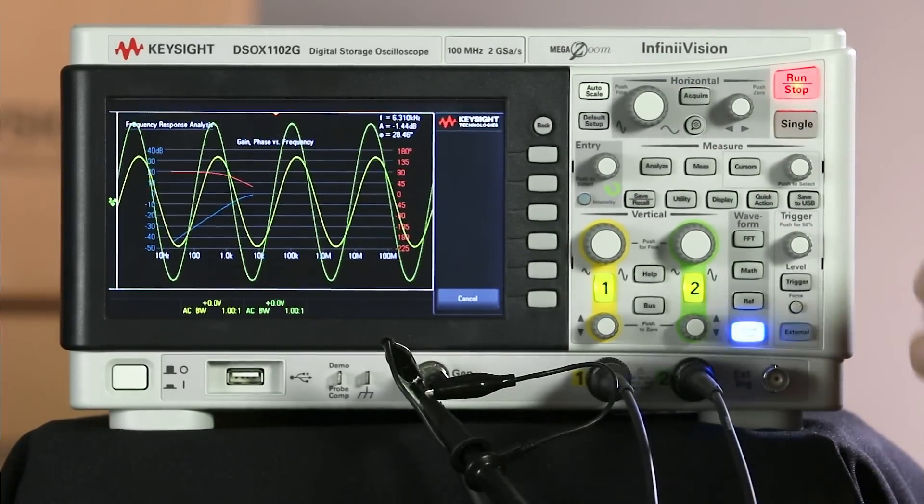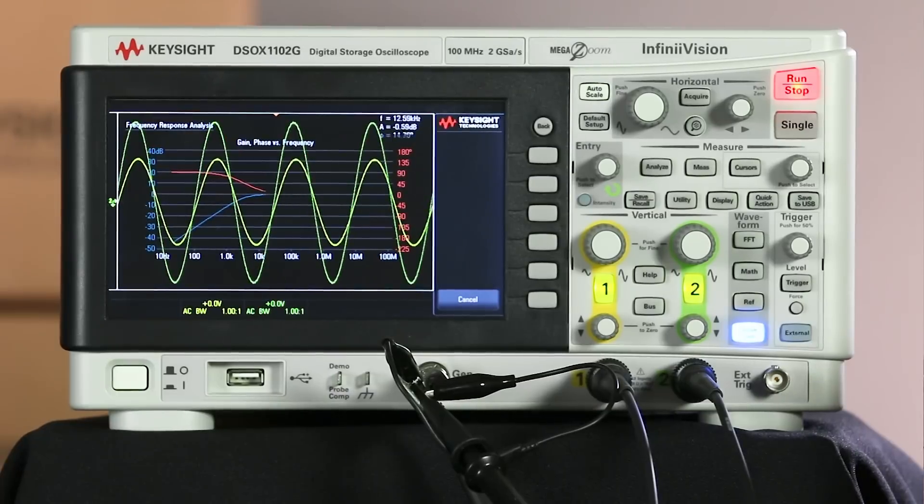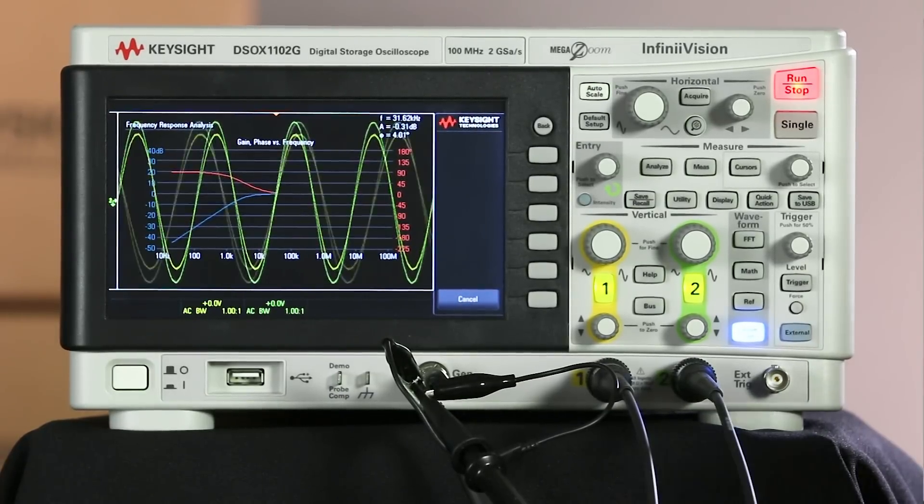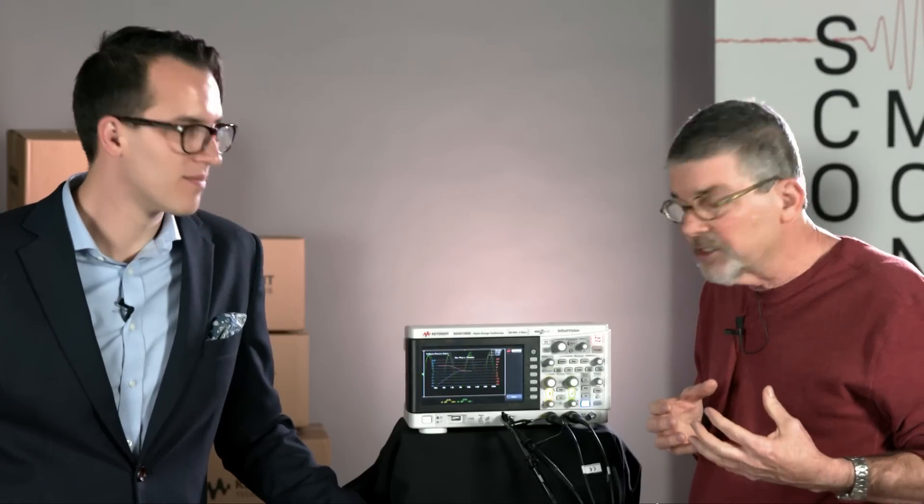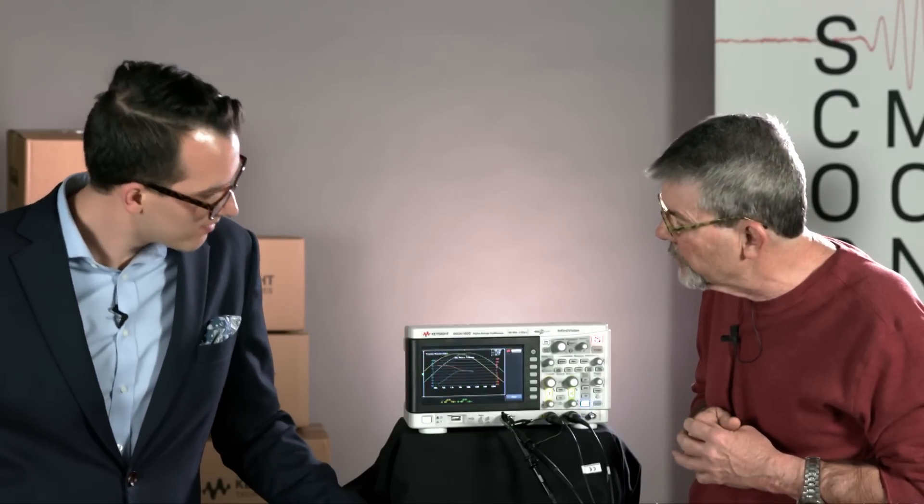Now, the spec is as much as approximately 80 dB. So the orange trace is the phase. Now, when it completes the test, and we're about two-thirds through now, as you go up in the higher frequencies, the test runs faster and faster. It runs pretty slow down there at 20 Hz.